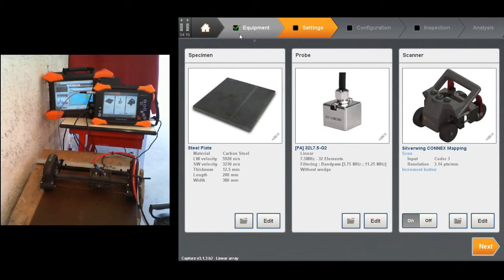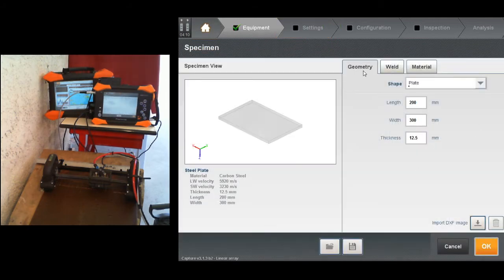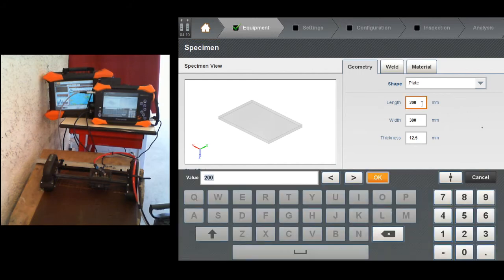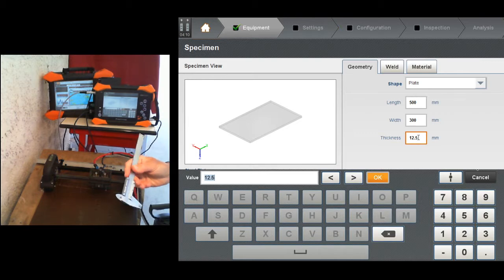The way the capture software is organized, we have different menus at the top, and we need to go through the different steps to have a complete setup. The first is equipment, and in equipment we have specimen. So the plate I'm going to inspect, I can select the probe and the scanner. Select the plate at first, and I can give a geometry. Let's say my plate is about 500 millimeters long, 300 millimeters wide, that's good. Thickness, measuring this with a caliper gives me 12.5.